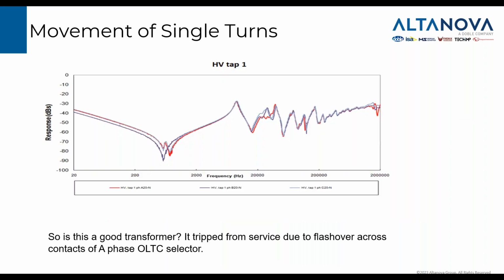But it's quite often not that obvious. This is an example of minor movement, just a few turns moved, and the transformer was potentially able to take a voltage and take a load, but fortunately we picked it up in time and it was not energized anymore. The transformer failed in service, it tripped, and flashover marks across contacts of A phase of the tap changer selector were found.